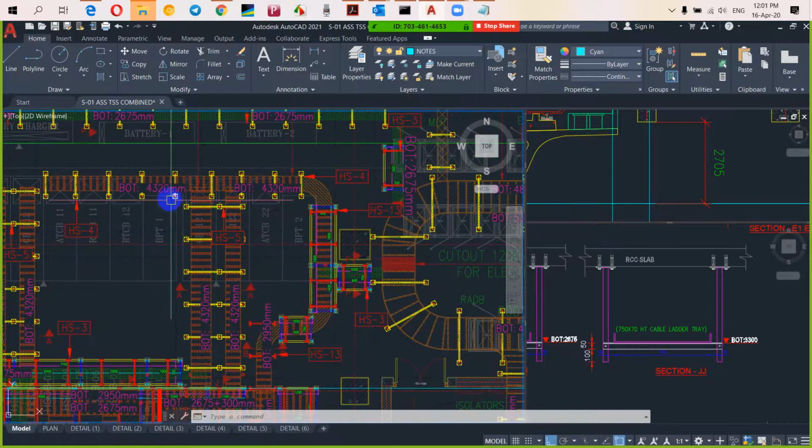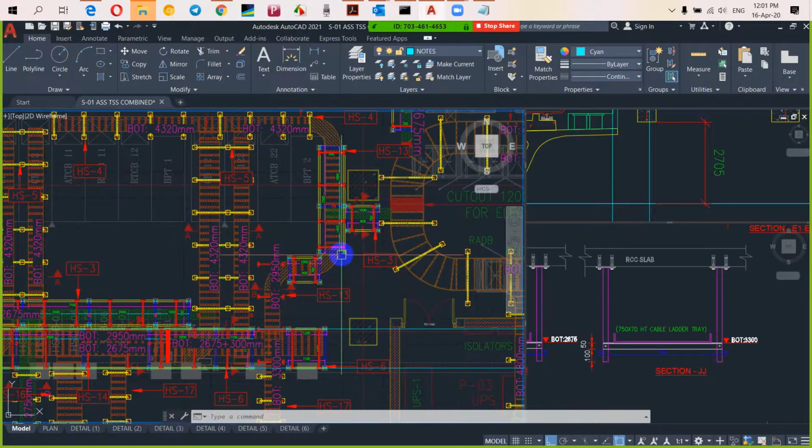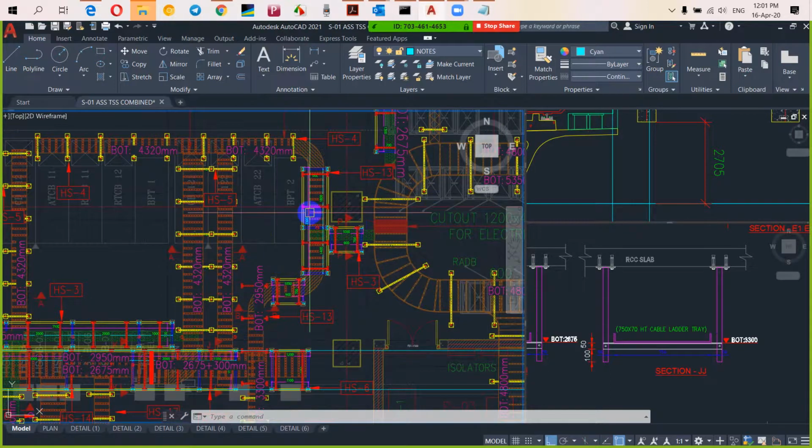So let's discuss this. So these cable trays are 4320, again 4320 coming. This we are having 4320 again. And the way that you have shown as 4320. The behind tray shall be 3300, right? So here it will be 3300. Yeah. Can I control this your screen? No. I'm not sure. Maybe no. So this area, 33. So not only there, the complete tray from the starting, like behind HS4. You can see HS4. Yeah, the entire branch should be the 3300, 2950.